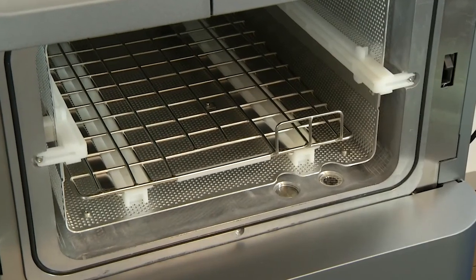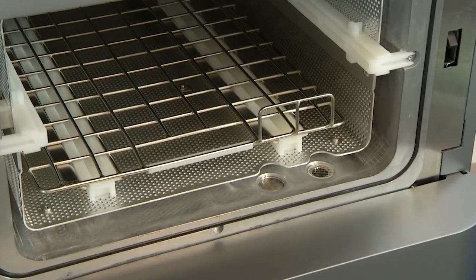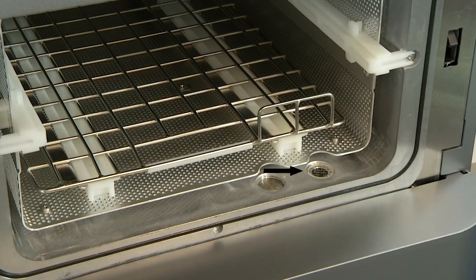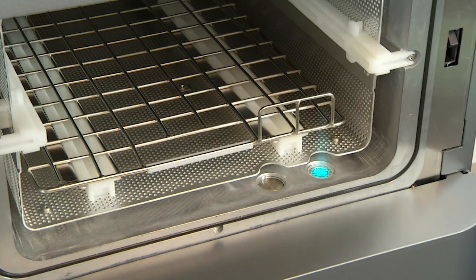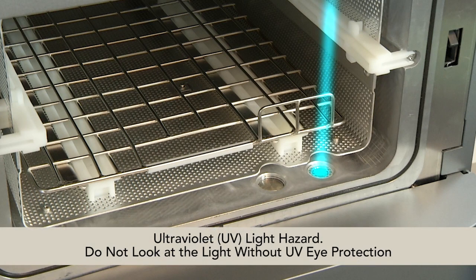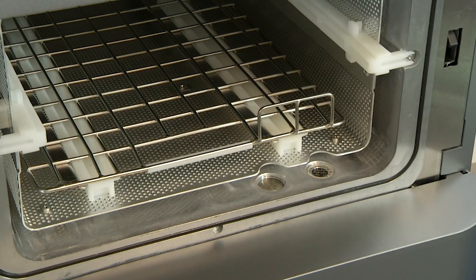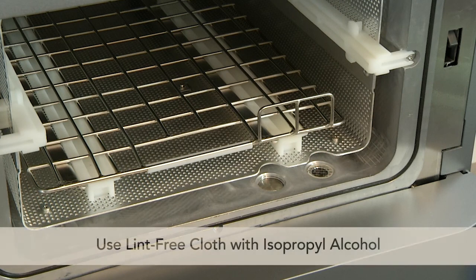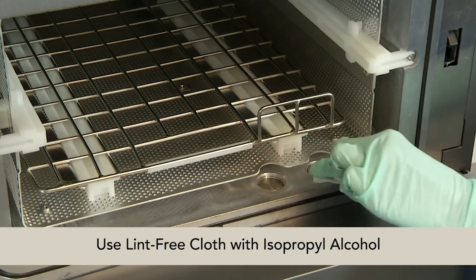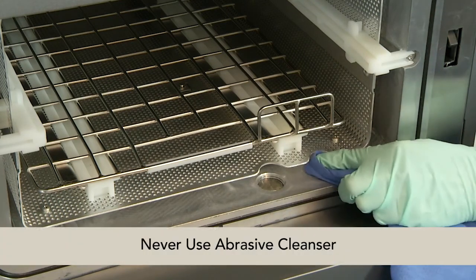Let's talk about maintenance. The hydrogen peroxide monitor lens is located inside the opening and must be kept clean. Clean the lens once every 3 months or when an accumulation of debris is present. Be advised that the hydrogen peroxide monitor uses an ultraviolet light source located inside the chamber behind the door. To avoid eye injury, do not stare directly at the ultraviolet light source for an extended period of time. To clean the lens, first put on chemical-resistant latex, PVC vinyl, or nitrile gloves. Then moisten a lint-free cloth with isopropyl alcohol and wipe the lens to remove any accumulated debris. Never use an abrasive cleanser.